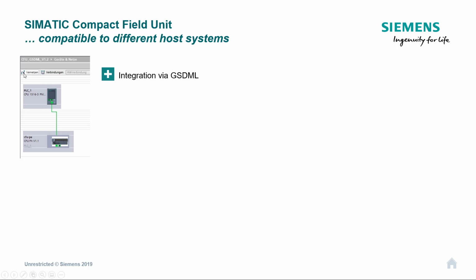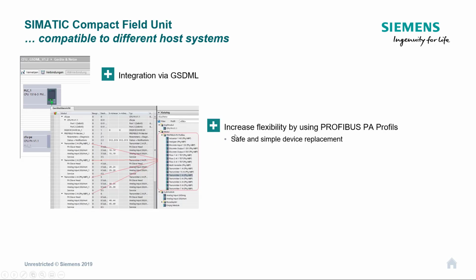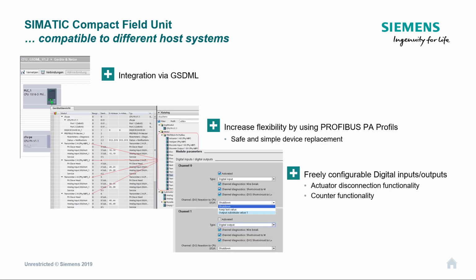Some of the things, it's all available on the site, the support site, the GSD ML for TIA portal. It's already in the PCS7 library, so if you're using PCS7 version 9, it will be in there, so you don't have to worry about going looking for it. It uses Profibus PA standard profiles, and these aren't Siemens, by the way. Siemens haven't written these. These are the standard Profibus International profiles. Okay, so if you go onto Profibus International and look for the generic profiles, you will find them on there, and they're no different to what we're using on the Compact Field Unit.